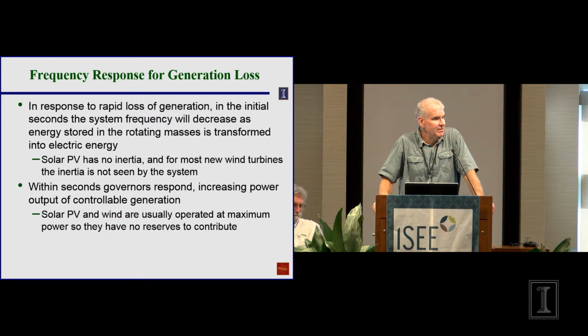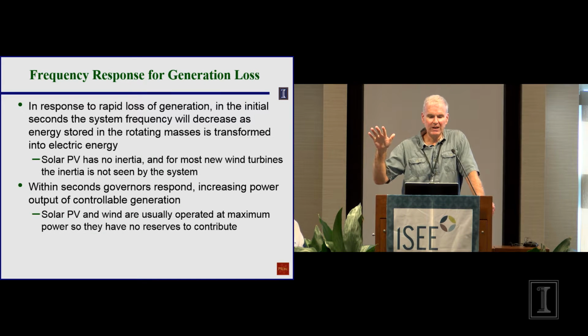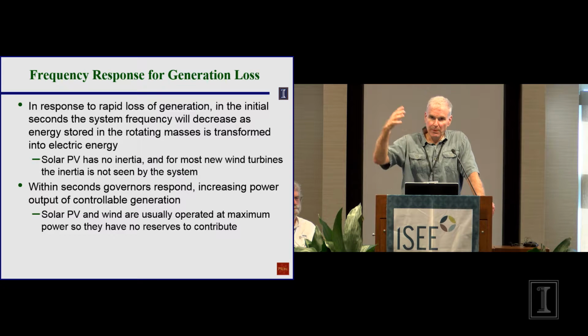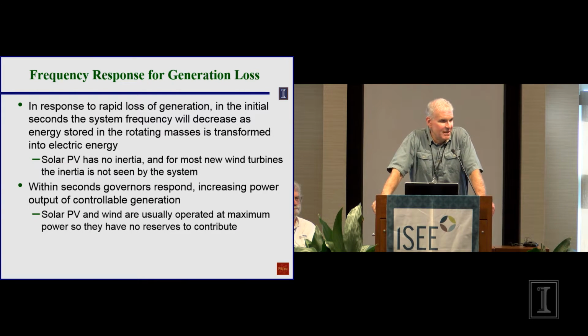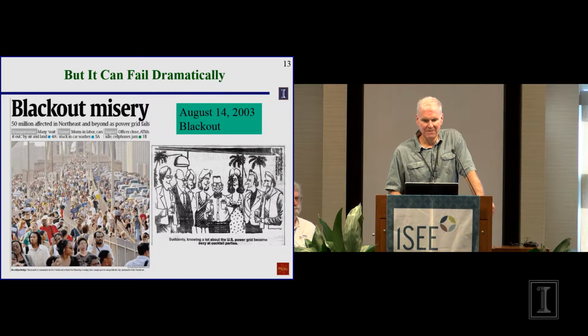What prevents the frequency from declining too fast is the inertia in the system. We have a lot of synchronous generators, like on a coal plant or a nuclear plant, that are spinning, so there's stored energy in the rotors of the machines. That helps stabilize our system. Wind turbines, for the most part, we don't see that inertia, and solar has none at all. So as we add more of this inertialess generation to the system, we get more and more challenges. As engineers, we like challenges.